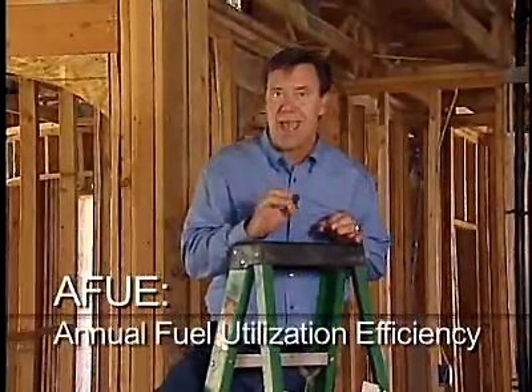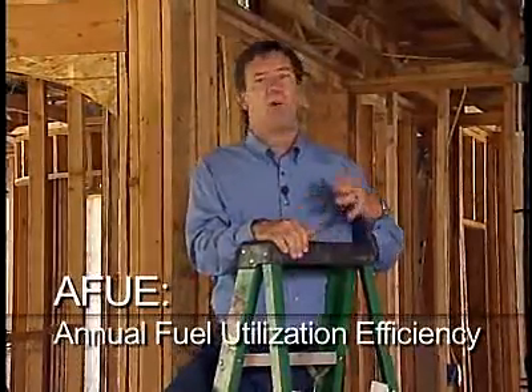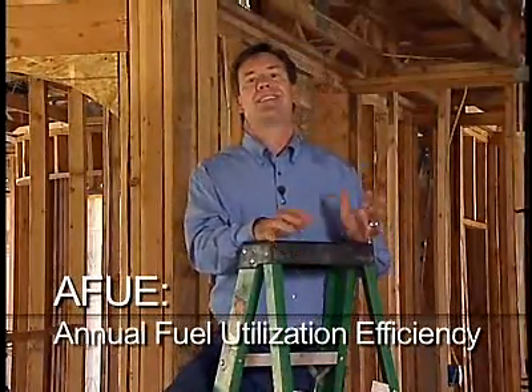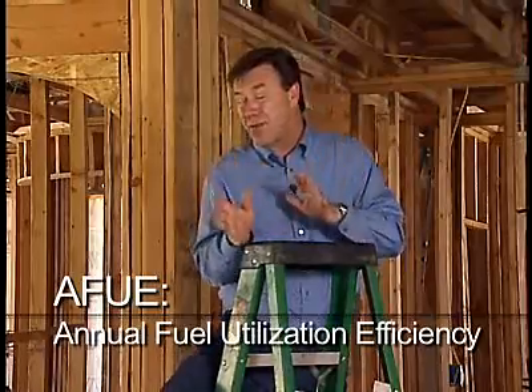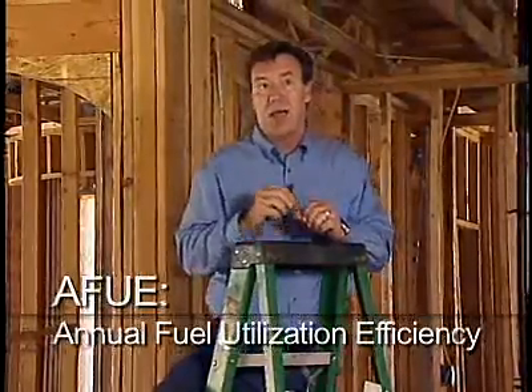Now, furnaces are rated in efficiency by what they call the annual fuel utilization efficiency, AFUE. A typical older furnace may have an efficiency of about 65%. That means that about 35 cents out of every dollar that you spend on your heating cost goes up the flue. Some of the newer furnaces are anywhere between 80 and 96% efficient. So in a 96% efficient furnace, or what we call a condensing furnace, it's so efficient that only 4 cents out of every dollar goes up the flue.